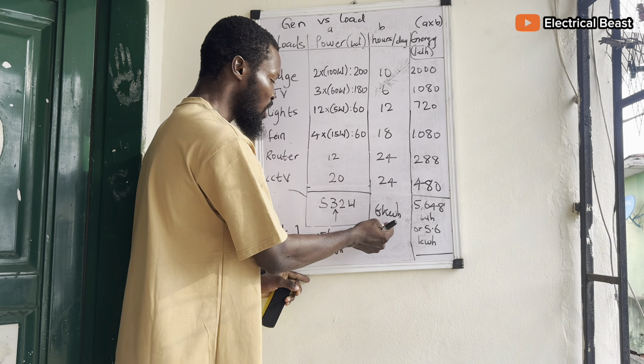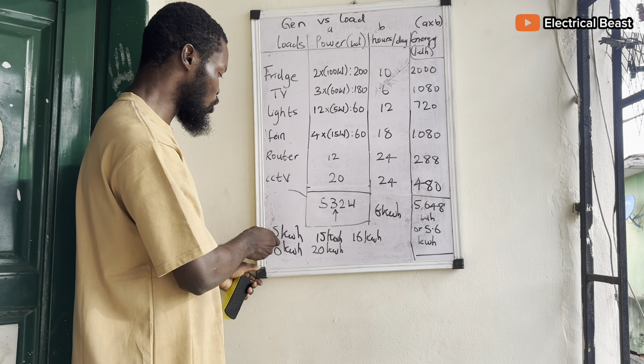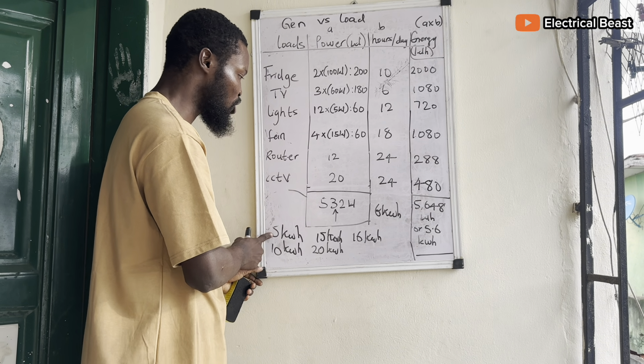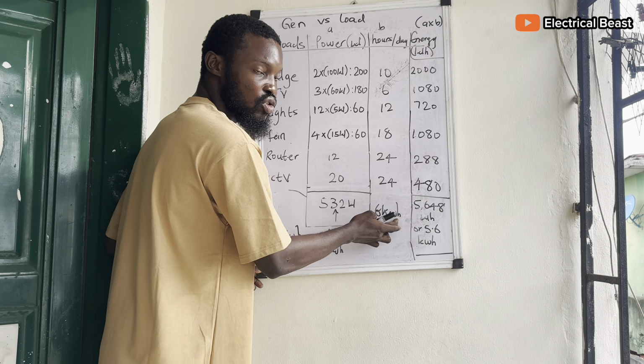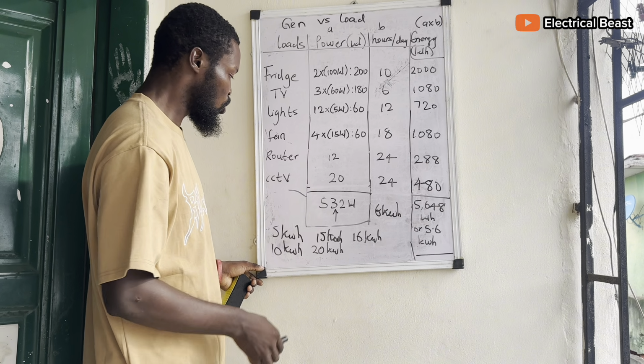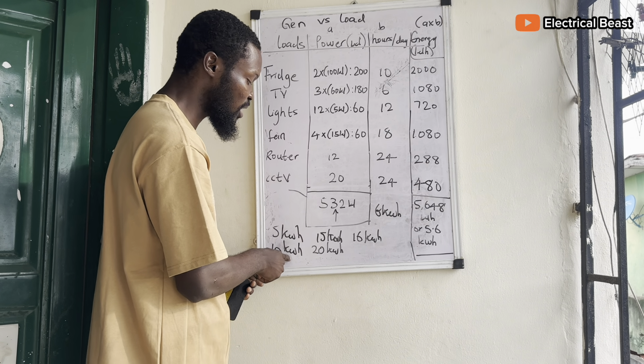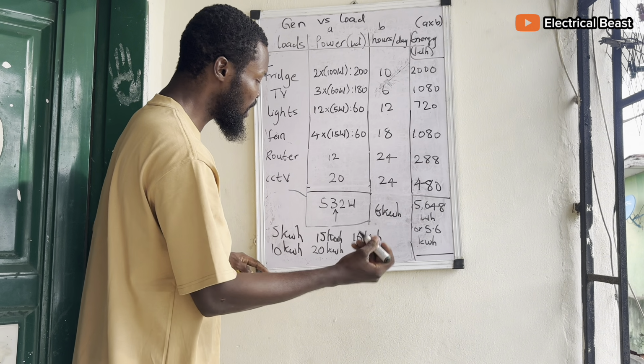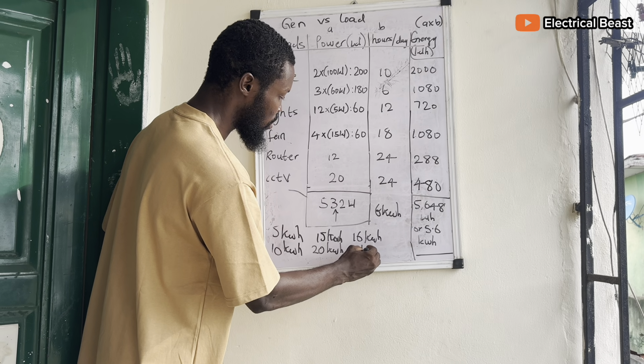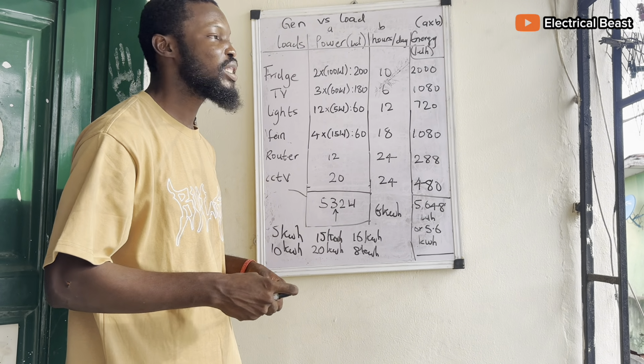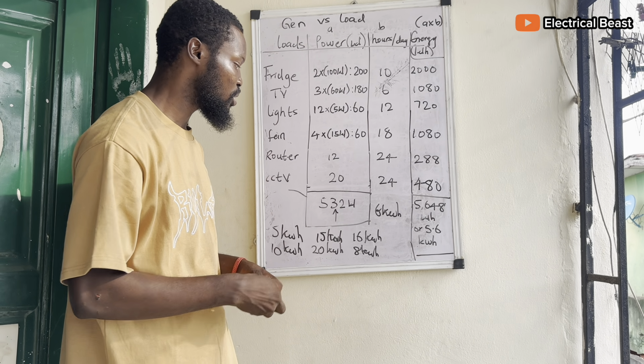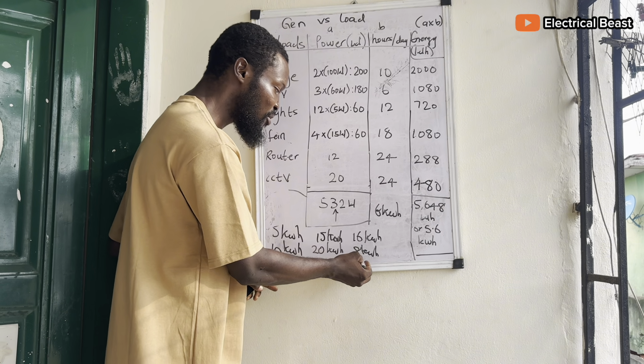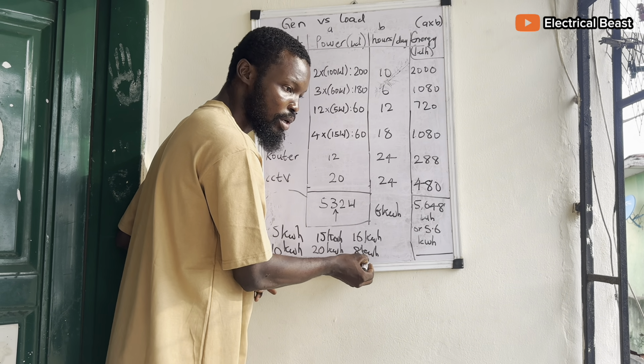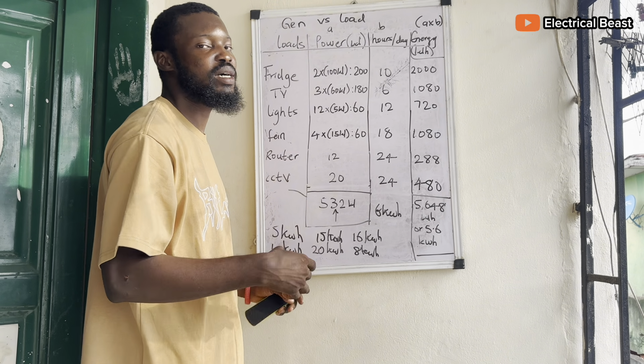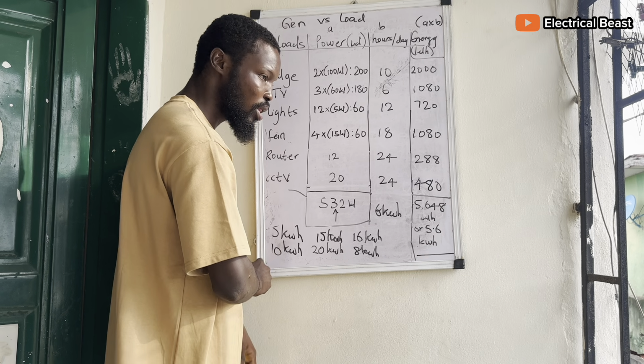So when you have 6 kilowatt hour, you need to know that you cannot go for 5 because the battery cannot be less than the daily energy consumption that you have. So we need to go for the next available one, which is 10 kilowatt hour. Also, there are some brands that have 8 kilowatt hour. But then again, in case you're looking at adding loads in the future, so that you have enough extra kilowatt hour to cater for those loads that will be added in the future. So we are going to go for 10 kilowatt hour.